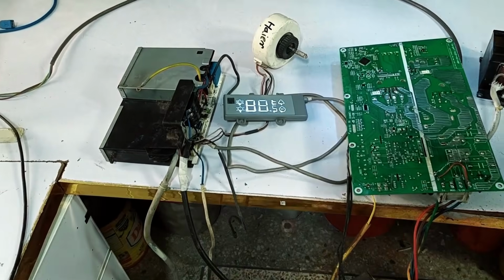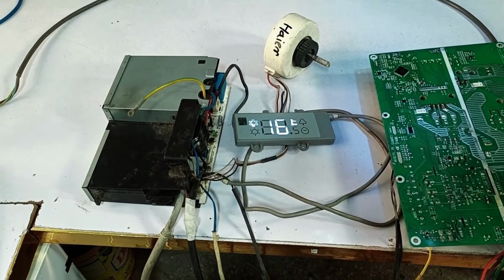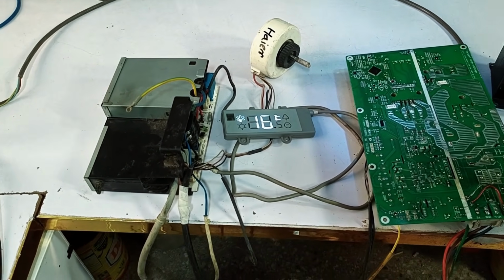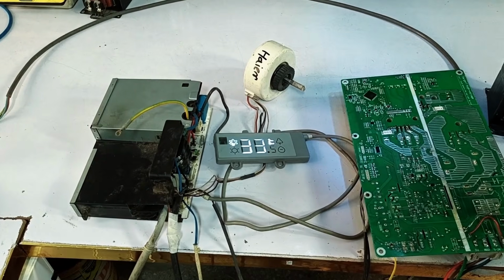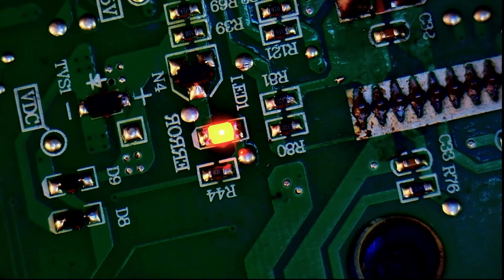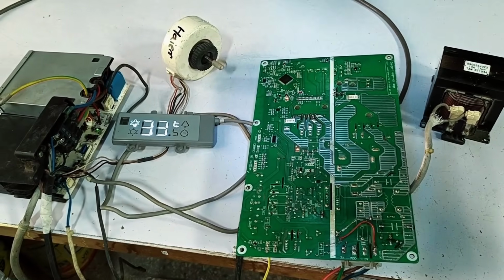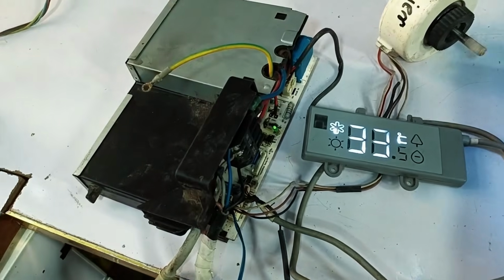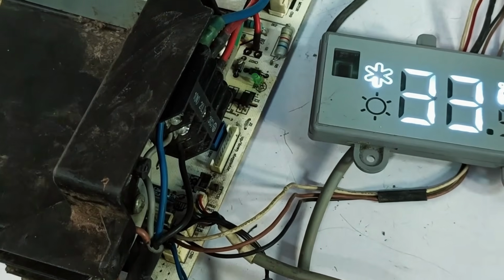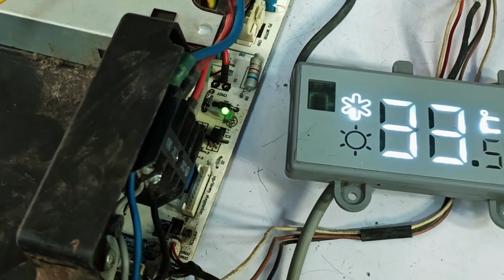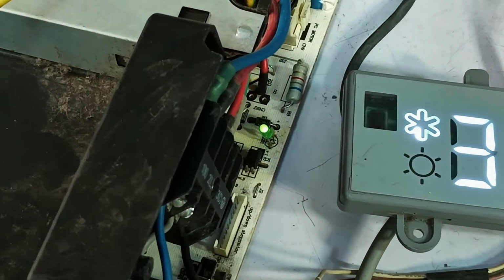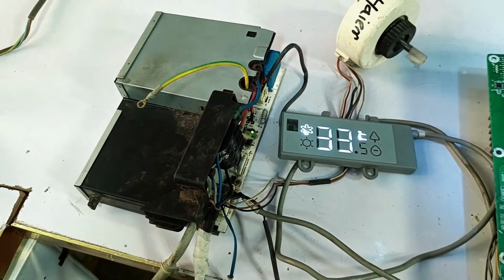And now it has turned on. It has started working at 16 degrees Celsius, and the outside temperature is 33 degrees Celsius. The outdoor circuit has powered on, and the indoor fan motor has started running. You can see that its communication with the indoor unit is working properly. In the indoor circuit, this LED is installed, and when it blinks, we can understand that communication is happening in the system.